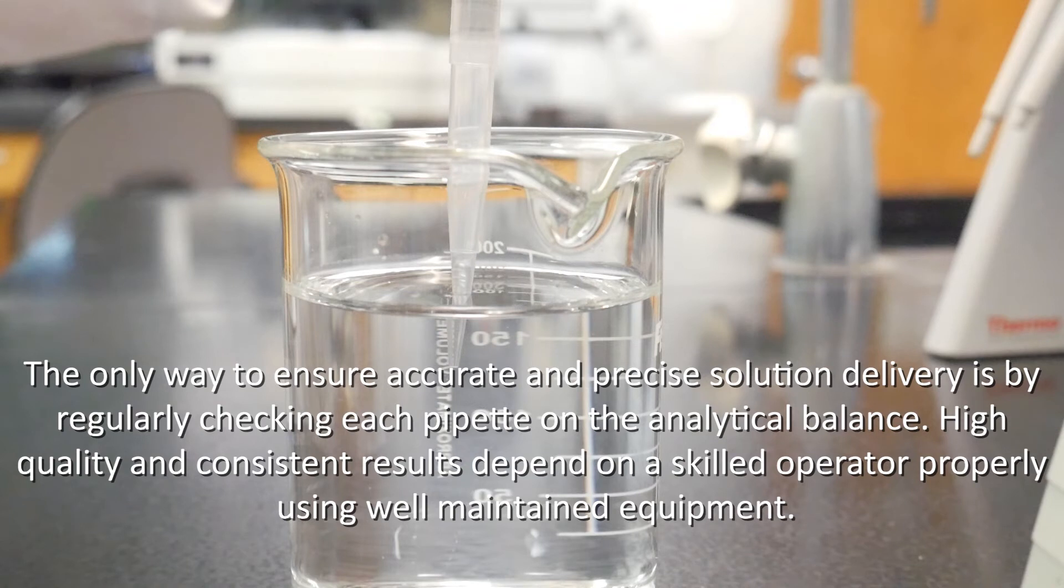The only way to ensure accurate and precise solution delivery is by regularly checking each pipette on the analytical balance. High quality and consistent results depend on a skilled operator properly using well-maintained equipment.